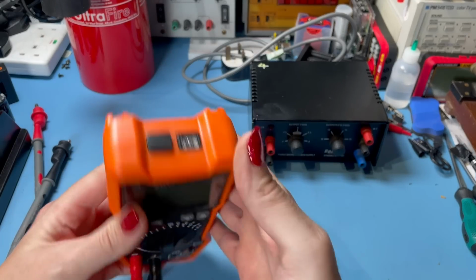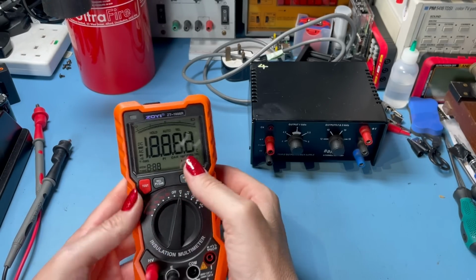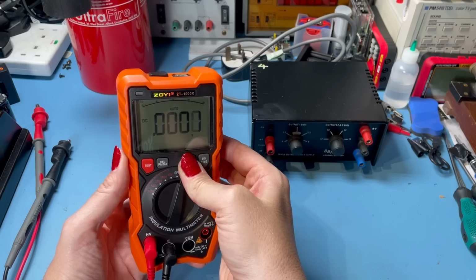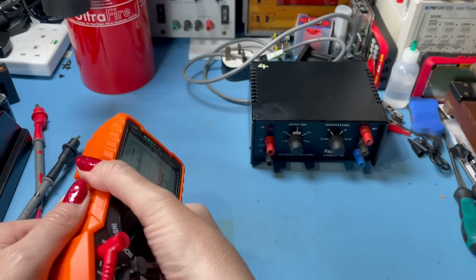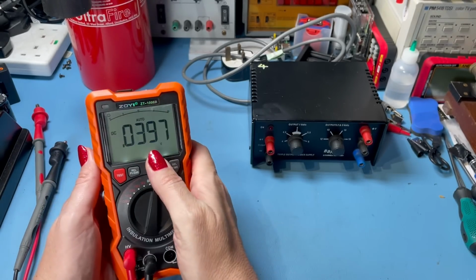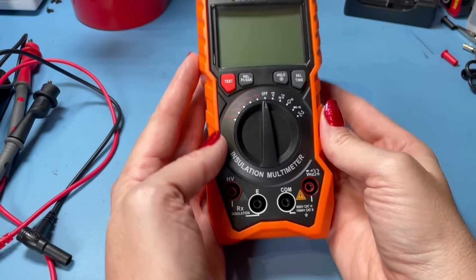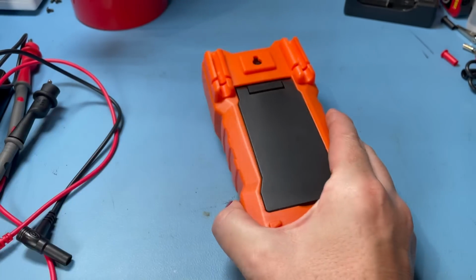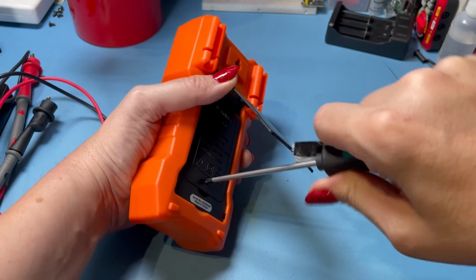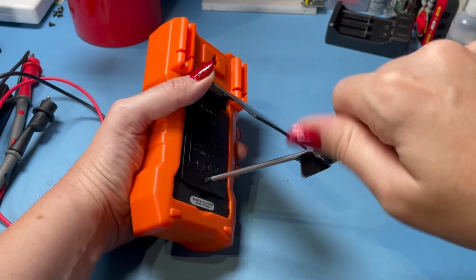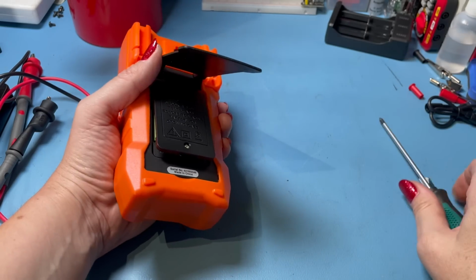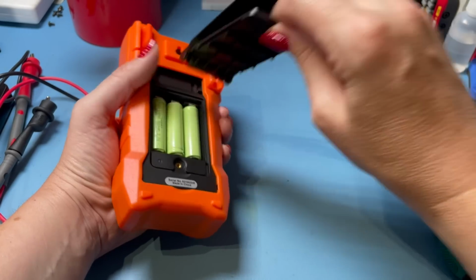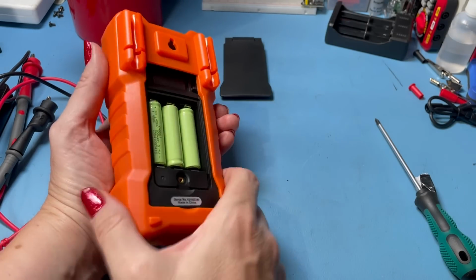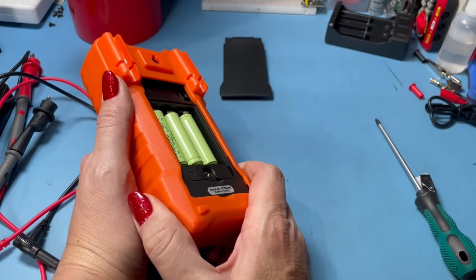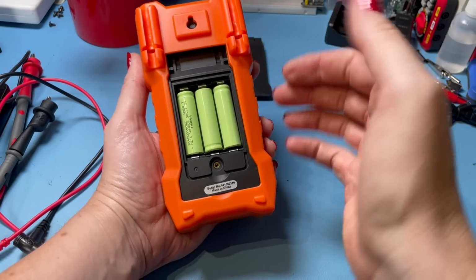It has got a light on the top as well, which I didn't really say much about. When you put your backlight on, you also get a little torch on the top as well, which might be enough to see what you're doing in a dark cupboard. Right, so one thing we've not really looked at is the batteries on this. So you have to undo this little screw here to get the rechargeable batteries out. Now, I think it's very sensible that Zoyi have done it this way because you don't really want to have a USB-C connection on something that could potentially be putting out 1000 volts. Now, that would be bad. So I think this is a really sensible way of doing it with the rechargeable batteries.